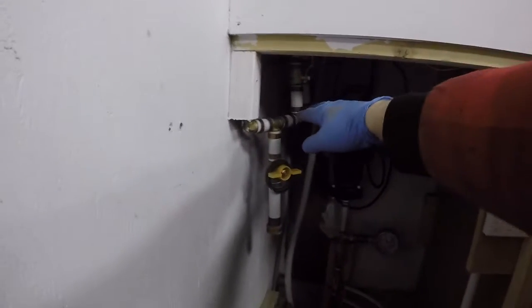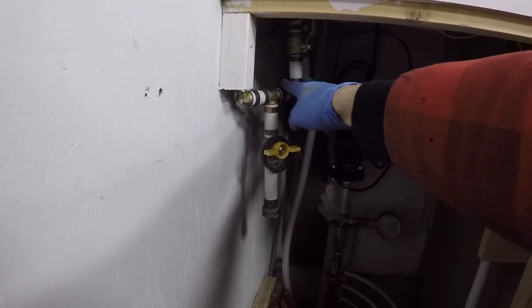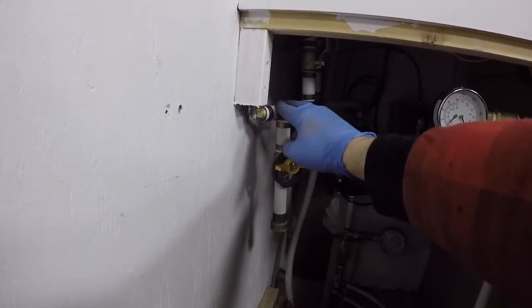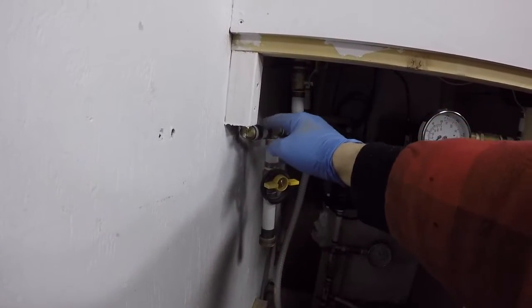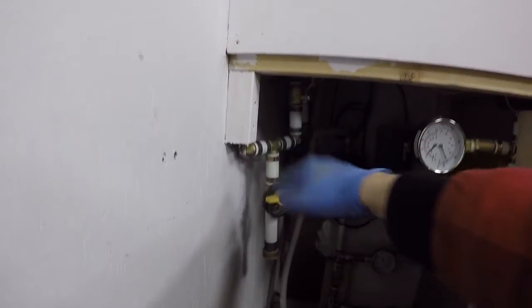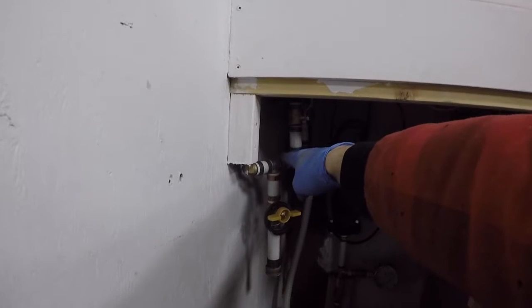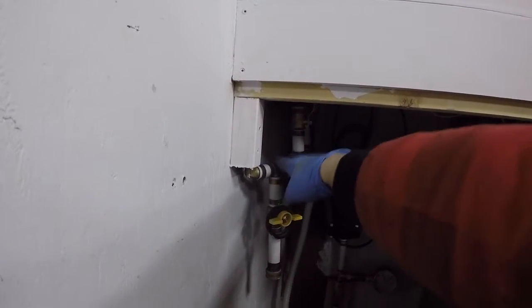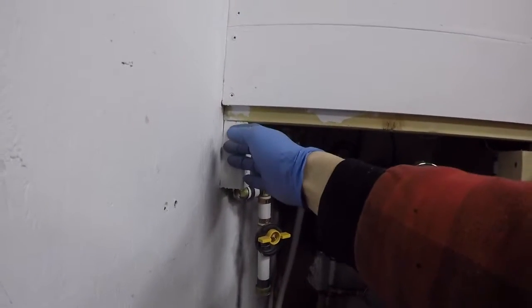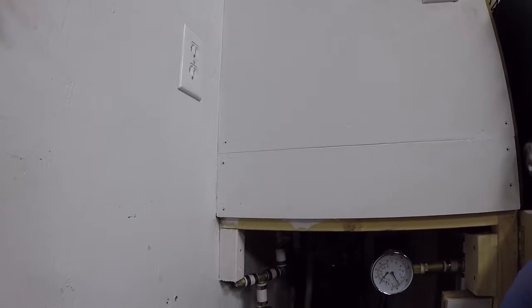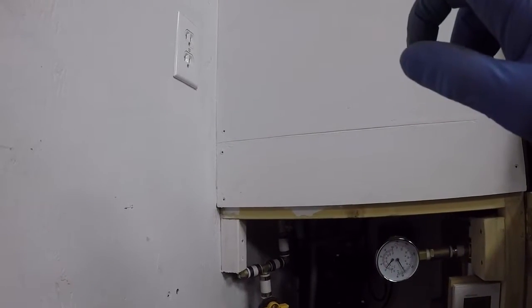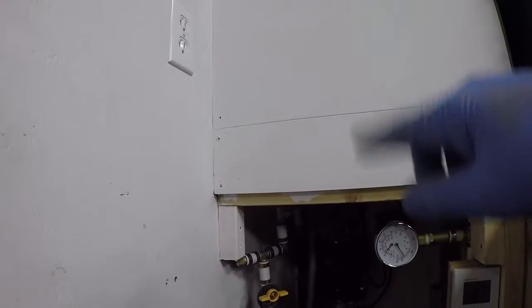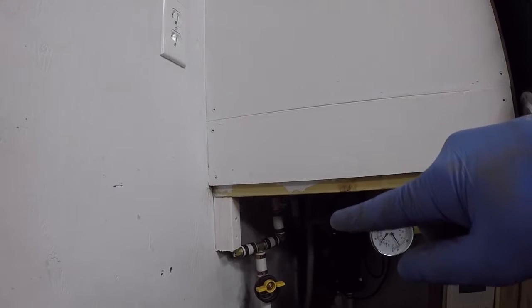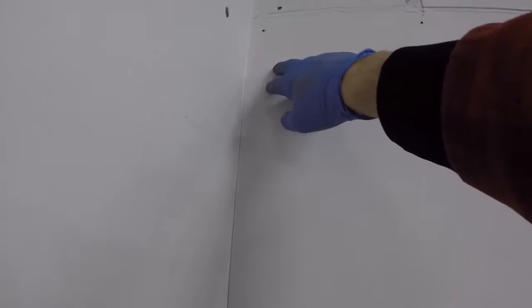So the water comes out of the bottom of the water heater, and say we've got a giant bubble in here for some reason. Well, the flow in this 3/4 inch tubing, when the pump is running, is moving at a pretty good pace. The flow of the water is moving fast enough through the 3/4 inch tubing that it is very easily going to push it over to this area. And we have 3 feet of vertical 3/4 tubing there, and we all know that air wants to rise in water. So the bubble naturally wants to go to the top, plus we have fast water coming through behind it, pushing it. So any air that gets trapped in there is automatically going to shoot up through this 3/4 tubing and across here.